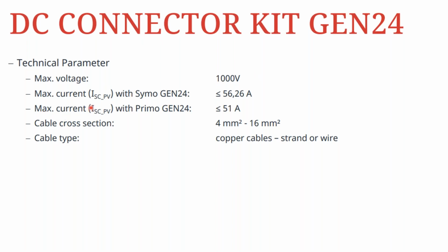For the short circuit currents, the Symo and Primo GEN24 Plus, the DC connector kit would be able to handle 56.26 and 51 amps correspondingly, and the cable cross-section area starts from 4 mm² and goes to a maximum of 16 mm². And the cable type, it's very important to underscore that only copper cables are allowed for connection to the DC connector kit, and this can be either stranded or single core cables.